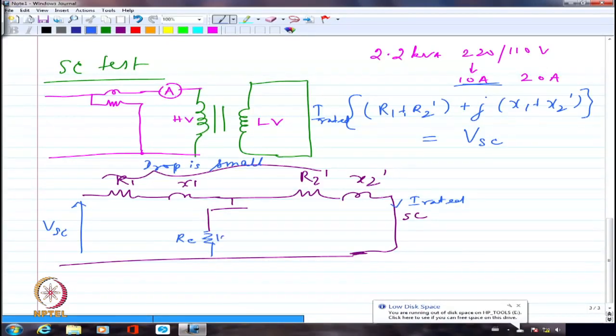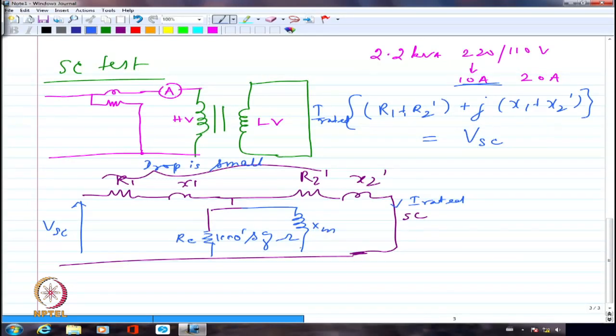Similarly, if I look at XM, XM is also essentially talking about the mutual inductance between the primary and secondary, in one sense, because that is the one which is talking about the common flux that is existing between primary and secondary. So if I don't have much of an air gap, obviously the coupling between the primary and secondary has to be pretty much intact. This XM value is an index of how permeable the core is. If the permeability of the core is pretty good, XM will be a very high value. So the higher the value of XM and the higher the value of RC, the closer and closer the transformer is getting to the ideal transformer.